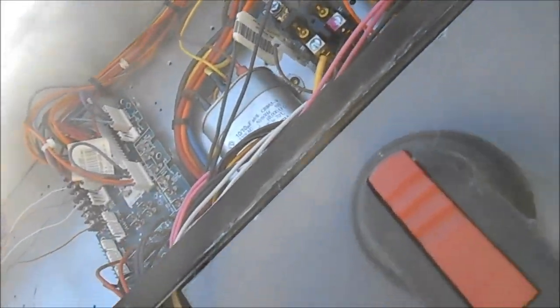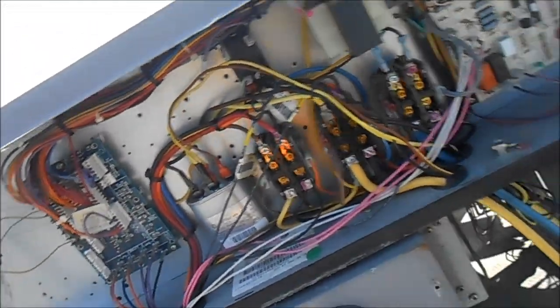There's 24 volts there. That primary will engage the compressor. This is the blower that's engaged as it's turned on, so it should be coming on but it's not. And when I engage that primary, the fans don't come on, so that's a little concerning to me as well.